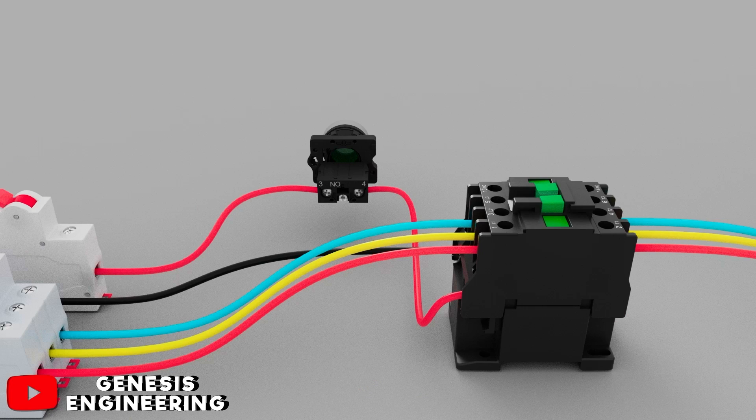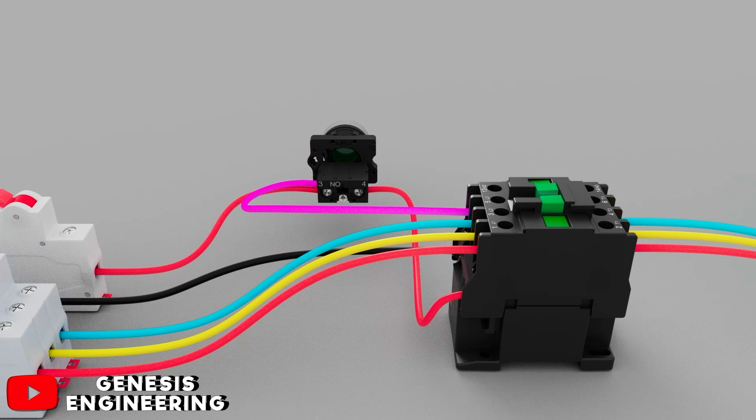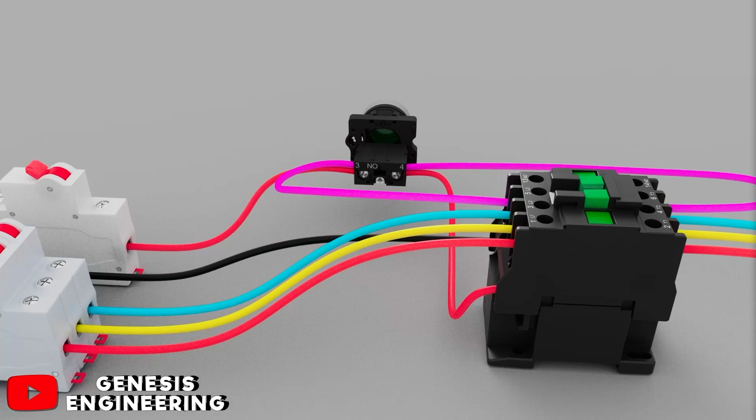Now to make the holding contact, let's keep the power circuit connection and change only the command circuit. Then we connect another conductor to terminal 3 of the button and connect it to auxiliary contact 13 of the contactor. On terminal 4 of the button we connect another conductor and connect it to auxiliary contact 14 of the contactor.